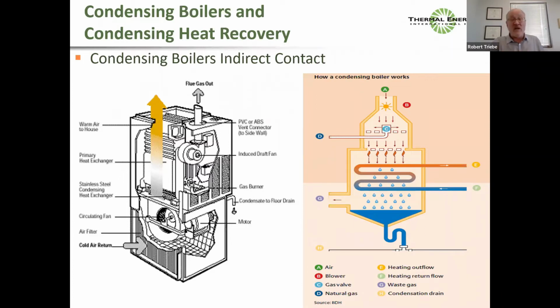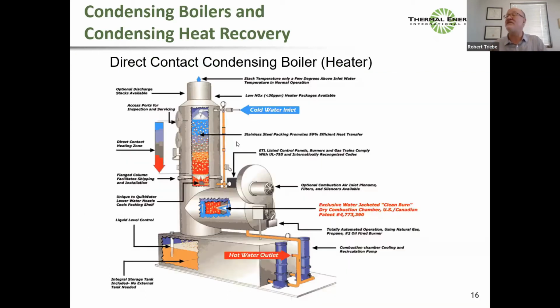Cold water in, hot water out. The cold water in is so cold that your flue gas is being cooled to below that dew point and you're condensing water out of the flue gas. That's common to all of these technologies. Another way to heat water, which is very interesting, is a direct contact condensing boiler. So it's the same thing. I'm heating cold water and I'm making hot water and I'm cooling the flue gas to below its dew point. But the difference is I'm doing it with direct contact.